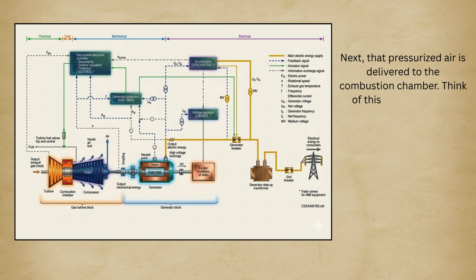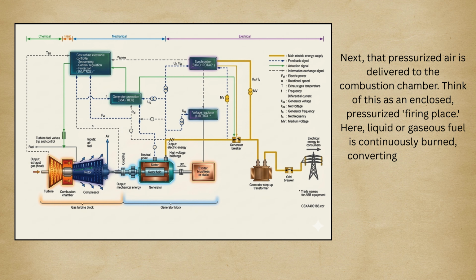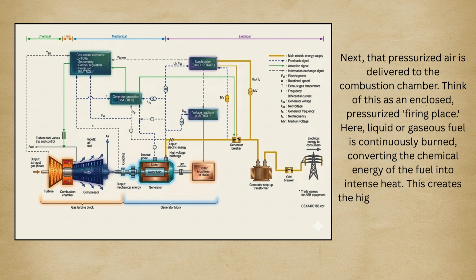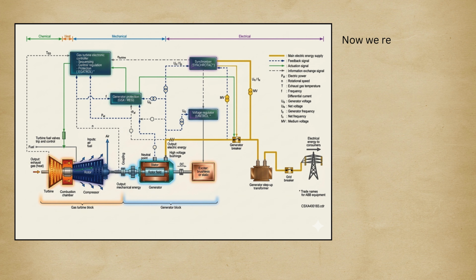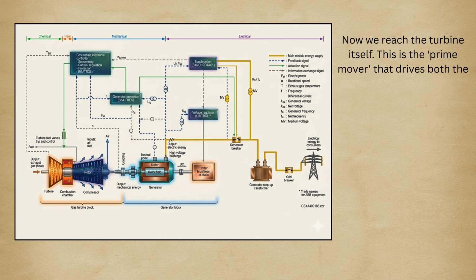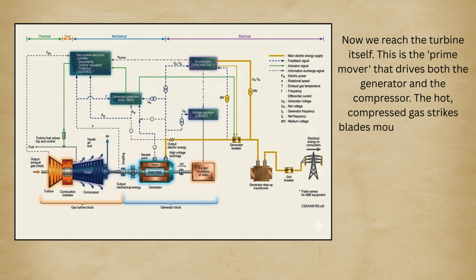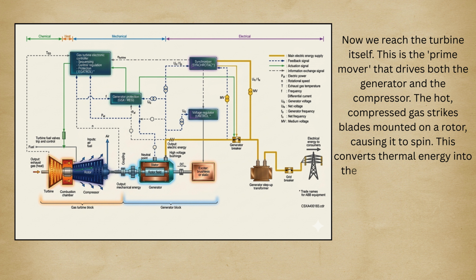Think of this as an enclosed, pressurized, firing place. Here, liquid or gaseous fuel is continuously burned, converting the chemical energy of the fuel into intense heat. This creates the high-energy combustion gas needed to drive the next stage. Now we reach the turbine itself. This is the prime mover that drives both the generator and the compressor. The hot, compressed gas strikes blades mounted on a rotor, causing it to spin. This converts thermal energy into the mechanical energy we need at the coupling.